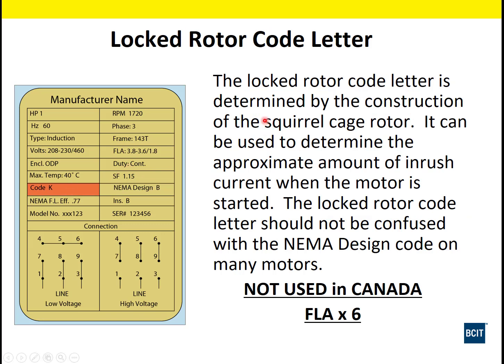Code K, it's a kVA locked rotor code. It's something that the National Electrical Code in the States uses for calculating inrush current. Down here at the bottom, we don't use it in Canada. We simply multiply the FLA by 6 times. Now, the way they calculate it is their FLA is going to be slightly higher than ours. I think we calculate for this guy here, it works out to 10 or 12 amps. In theirs, it would be around 14 amps or something like that.